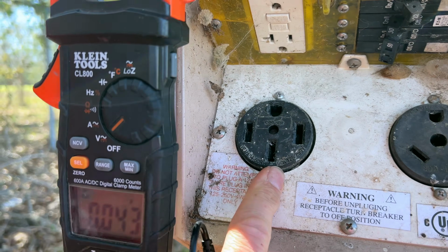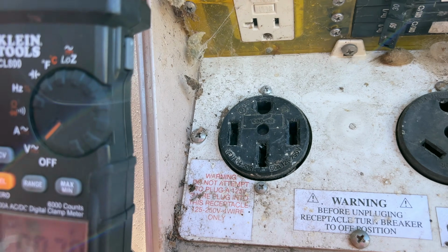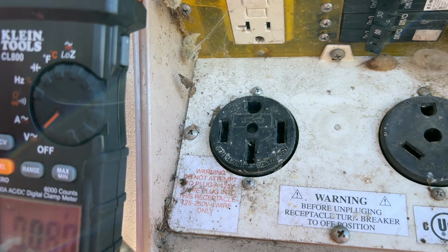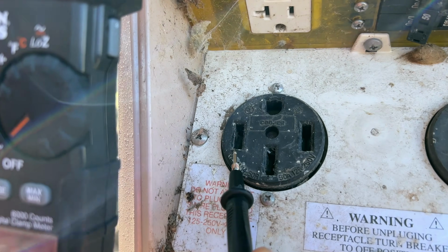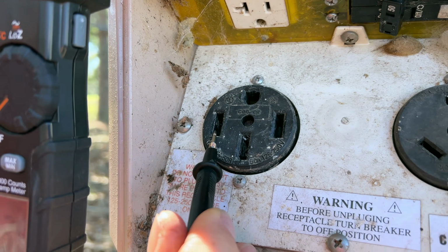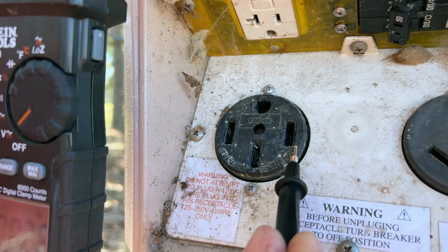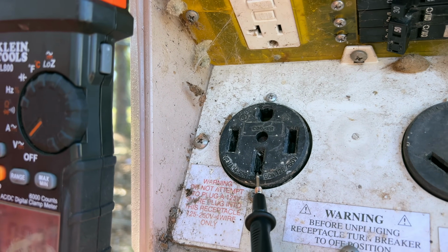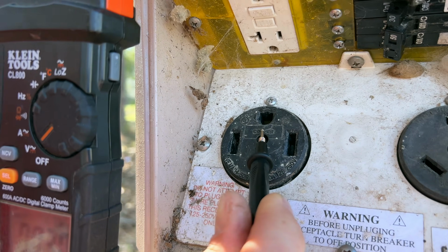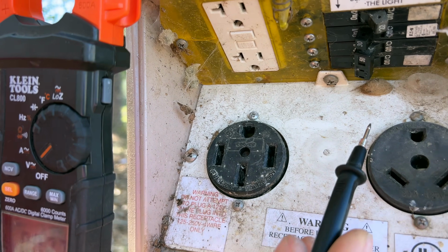Now switch over to our 50 amp side. So on your 50 amp plug, we have two hot legs that are right and left. So hot leg here, hot leg over here, and at the bottom is our neutral, and the top round is our ground, just like our 30 amp was.